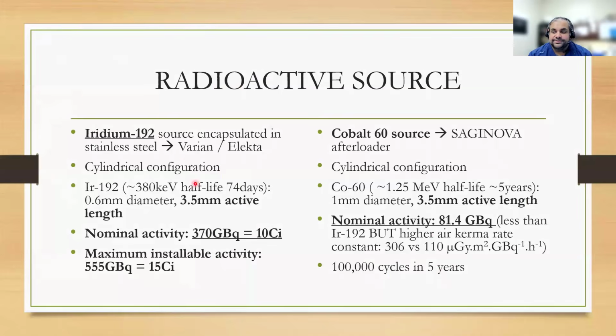So, just to reintroduce the previous slides and simplify it a little bit, we have iridium 192, which is quite common in North America. That is used for HDR brachytherapy. And then there's also the cobalt 60 source that's used in the Saginova afterloader. You can notice over here the nominal activity of the iridium is quite high compared to cobalt. However, the air kerma rate for the cobalt is a lot higher. And that takes into account the dose rate for the treatment when you compare both cobalt 60 and the iridium 192.